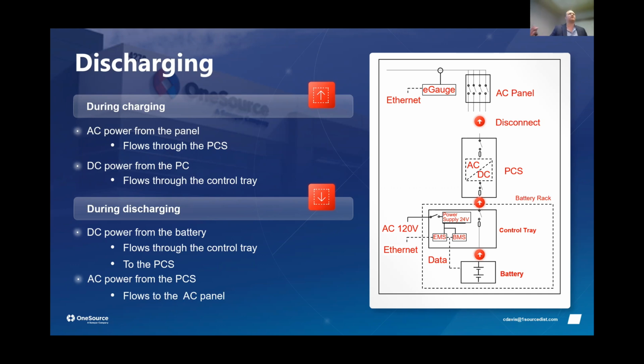Let's say we have it for peak shaving. We want 80 kilowatts at the facility, but if the facility is demanding 100 kilowatts, that's when we want to use the battery power to offset those 20 kilowatts. So the E-gauge meter talks to the battery storage energy management system, telling the battery to release its stored energy into the facility.